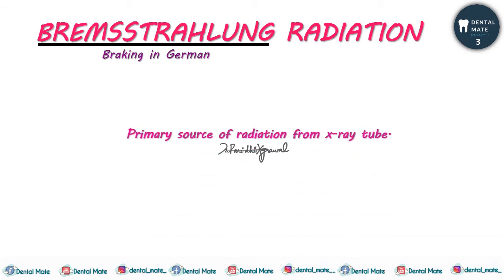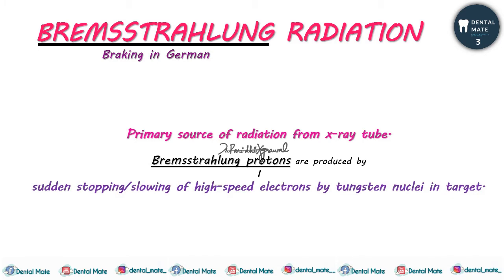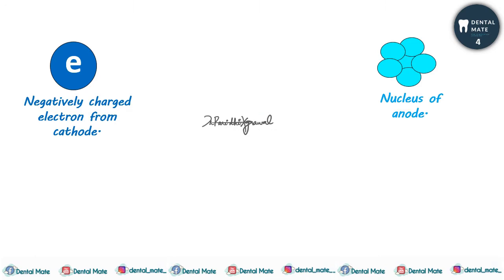Bremsstrahlung radiation is the primary source of radiation from the X-ray tube. Bremsstrahlung photons are produced by the sudden stopping or slowing down of high-speed electrons by the tungsten nuclei in the target. The tungsten target nuclei suddenly stop or slow down the high-speed electrons, and because of that Bremsstrahlung photons — X-ray photons — are produced.